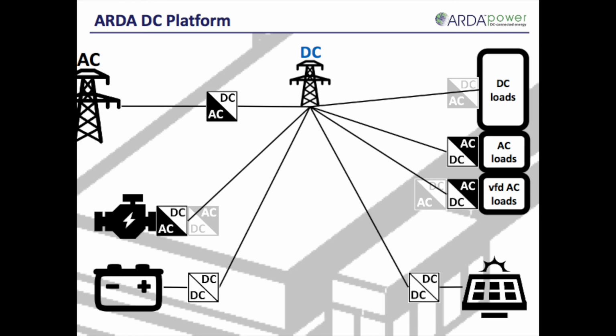The heart of the system is the battery DC-DC converter, which connects a storage device or devices to the DC bus and houses distributed microgrid controls responsible for managing the system. The converter maintains nominal DC bus voltage using battery resources to rapidly respond to instantaneous bus voltage changes, and uses changes in mean voltage to communicate with energy sources and loads connected to the DC bus. This makes the battery converter a virtual microgrid controller and removes the need for a physical controller.